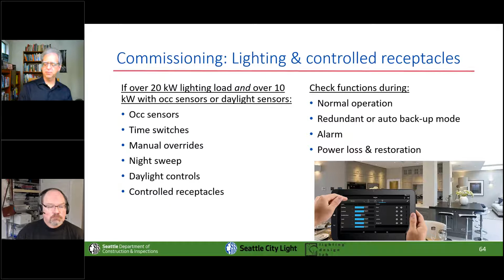So we're back to lighting for a minute. You have to commission your lighting controls if the project is over 20 kilowatts of lighting, and more than 10 of that is controlled by daylight sensors or occupancy sensors. With current lighting, 20 kilowatts would be about 30,000 square feet of area. As you've probably noticed, just about every place has occupancy sensors or daylight sensors, or maybe both, so this really needs somebody who knows what they're doing to do the commissioning. And note that while you're at it, you have to commission the control receptacles to verify that they actually turn on and off when they're supposed to.